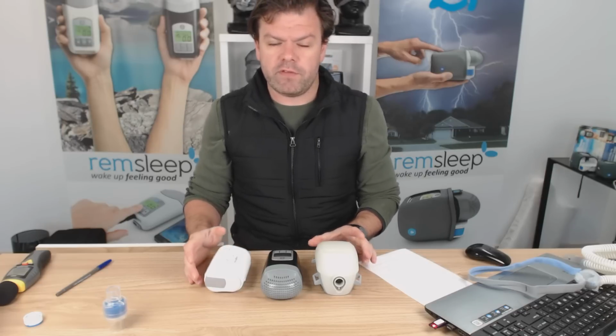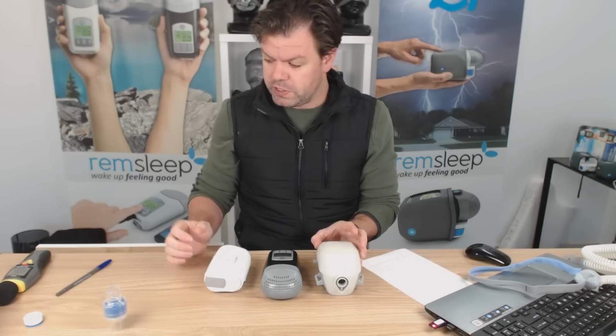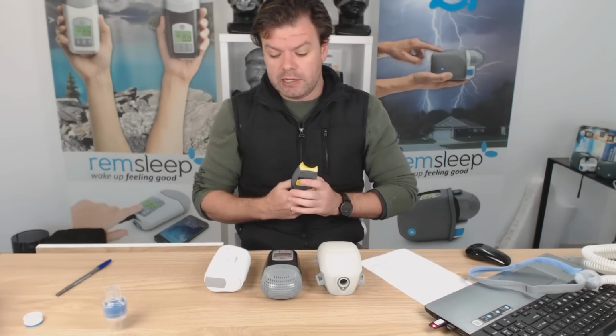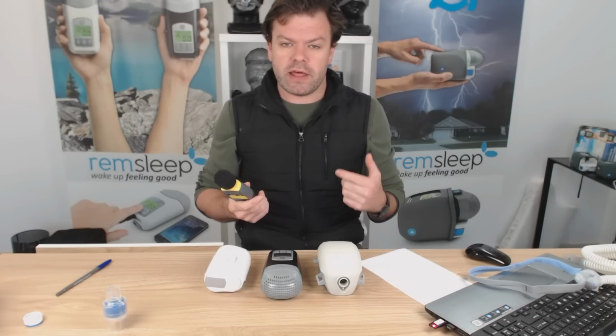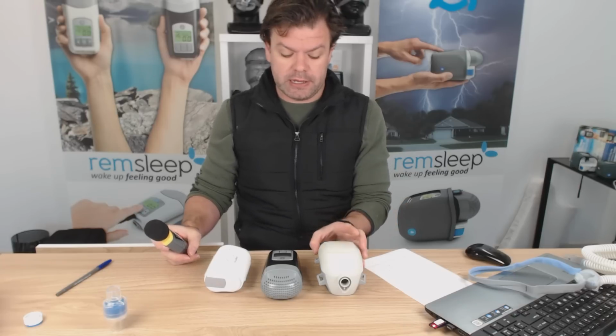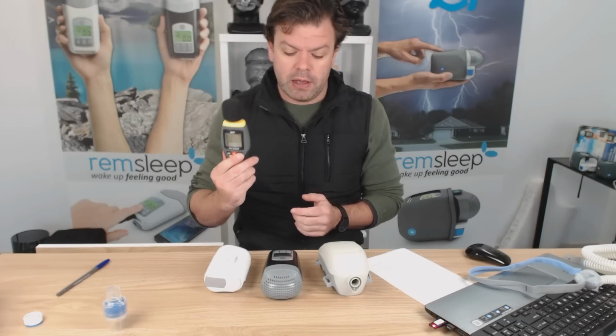When it comes to noise level, if you look at my AirMini video, you would have seen I used this little device, which is the decibel recorder, just to give you a realistic expectation of the noise levels. They are a little bit noisier than your standard full-size machines. I've gone through that before. And the manufacturers, when they give out those decibel readings on their little specifications charts, are very misleading. They will give you numbers like 26, 29, very, very low numbers, where ambient room noise, if I just very quiet ambient room noise is around 30 decibels. So the machine's obviously noisier than ambient room noise, so when I do this decibel meter, I use the same mask across all machines, set the machines to 10 centimeters, which is a nice middle of the range pressure, breathe the same on all of them.